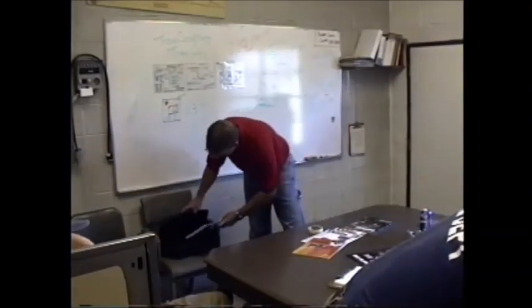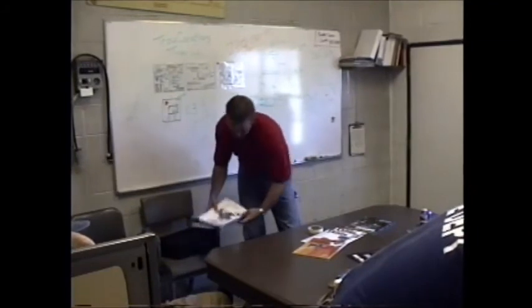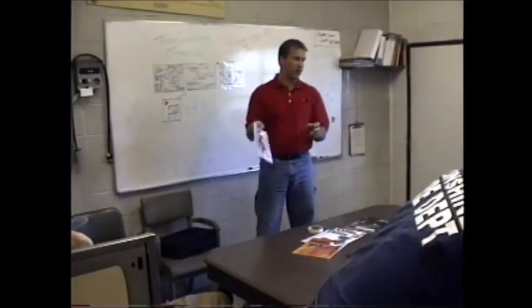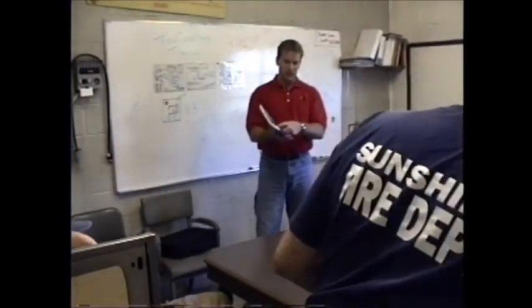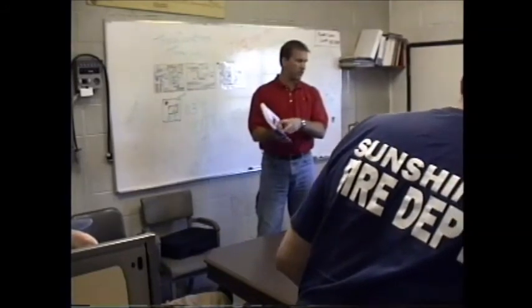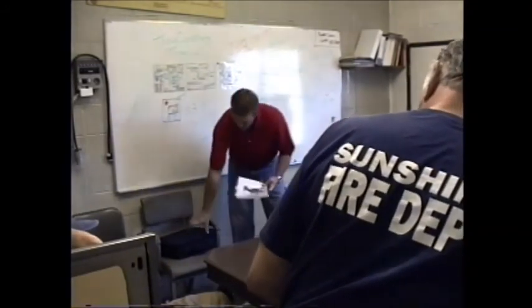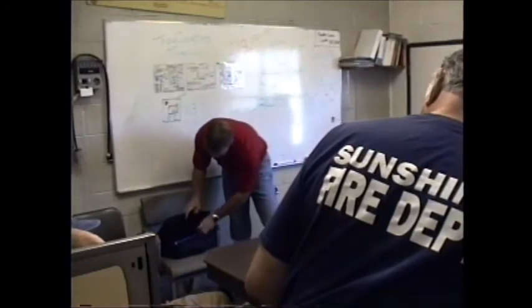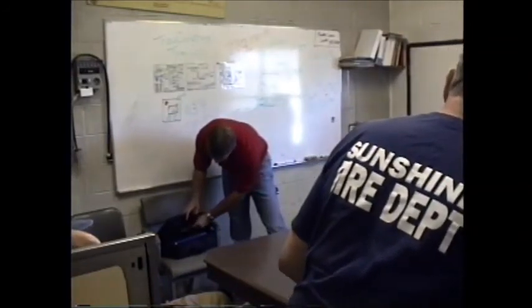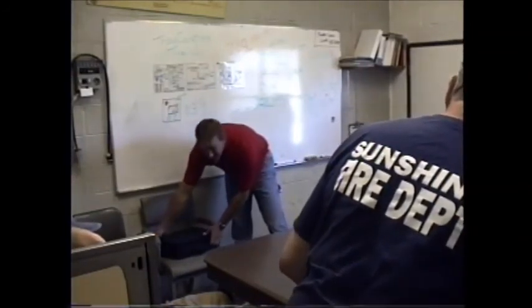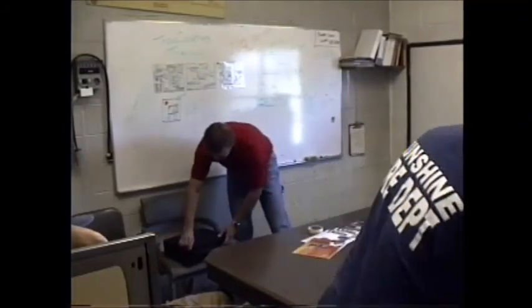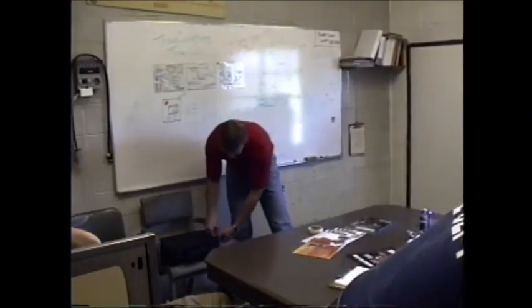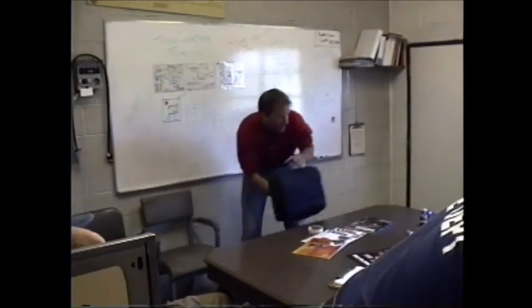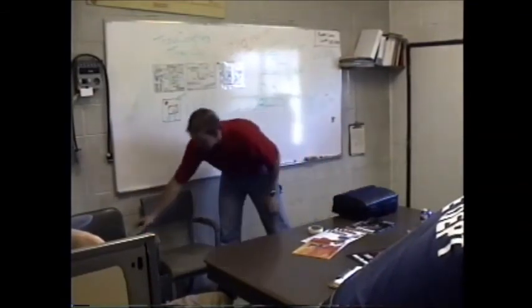There's no air control. This one's a little bit different. I'll leave this one here with you, so you have an extra one to hang on to. This one is actually our midship, it's not a PTO drive. The air filter check is every 25 hours unless you're in adverse conditions like a dusty environment. So that would be like twice a day under those conditions. If you're running that pump full time, we want to have one with us. I already put it on my list.